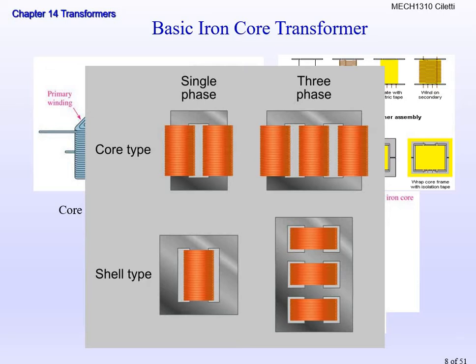So we can see what it takes for the windings of the two types of transformers. The two pictures at the top are for core type transformers—notice the windings are on the outside legs of the core. The bottom type is shell type. Single phase is on the left, three phase is on the right. We can see what the different windings look like and how they're enclosed in the transformer, and notice that three phase has a winding for each phase.